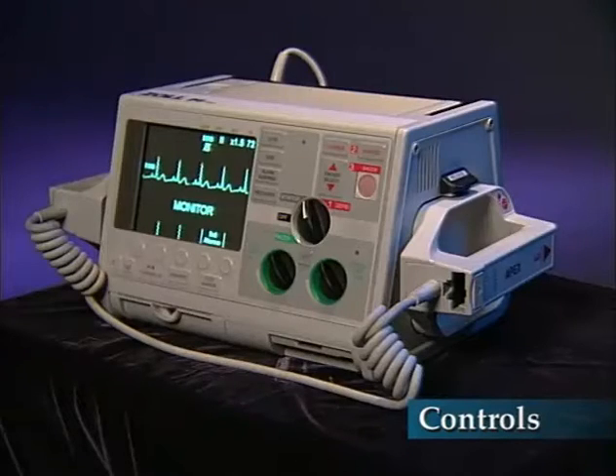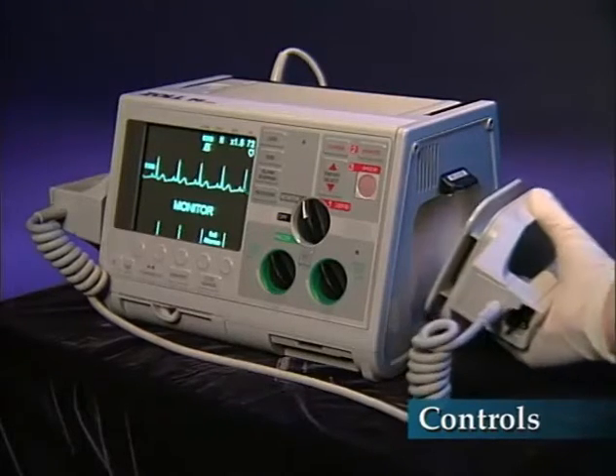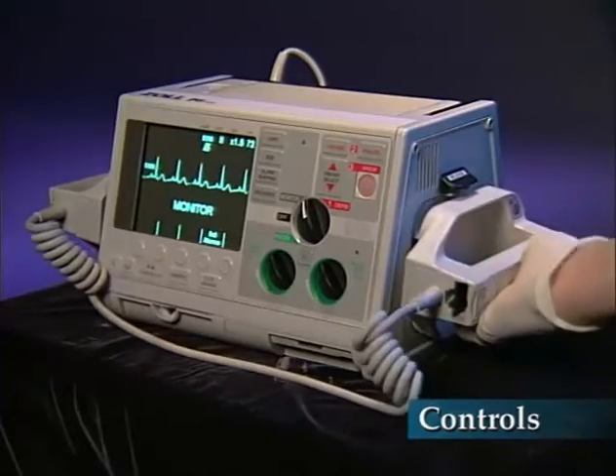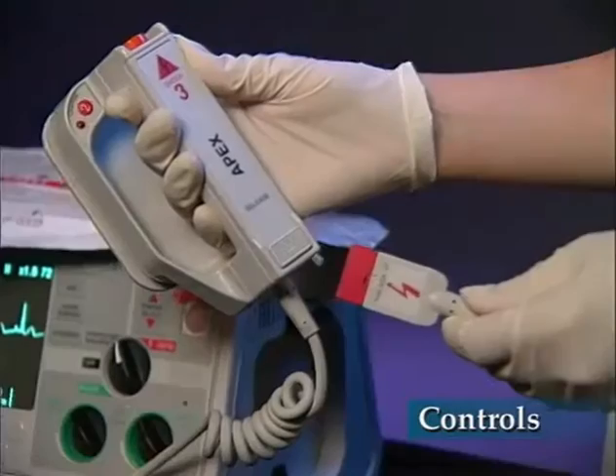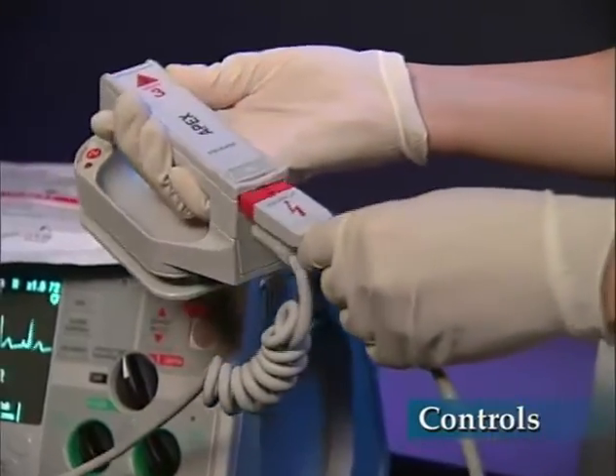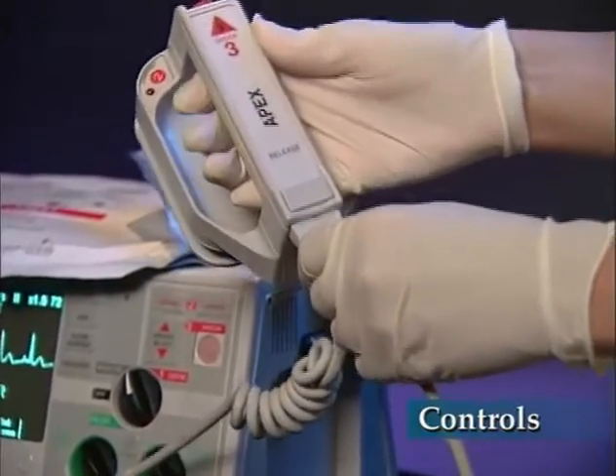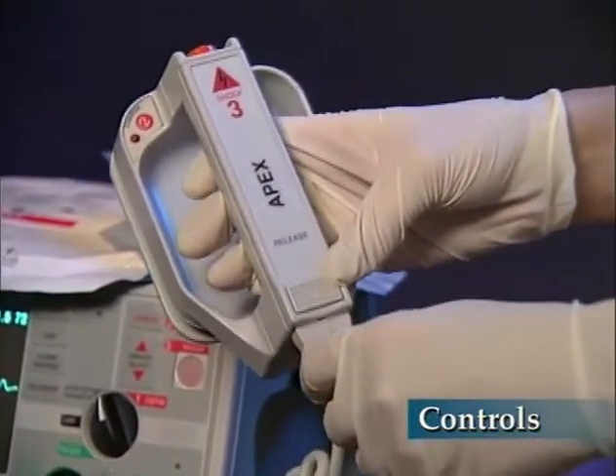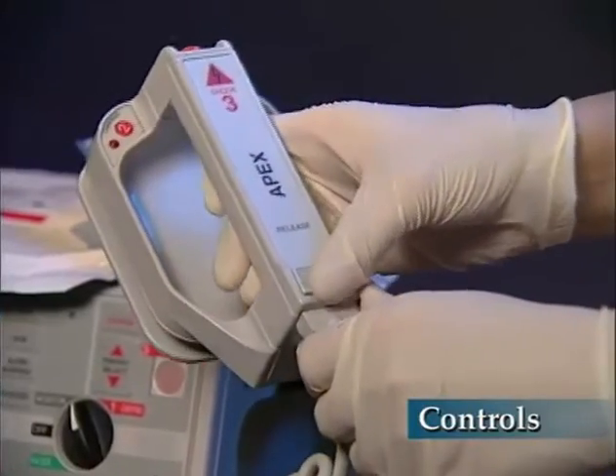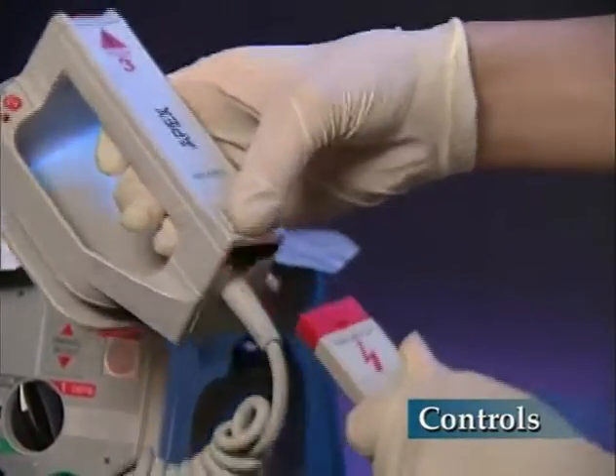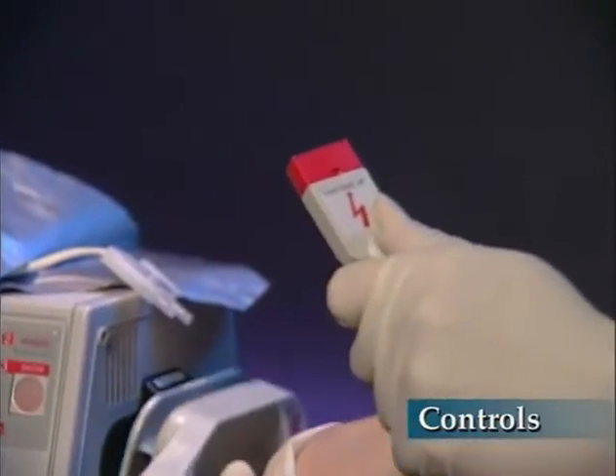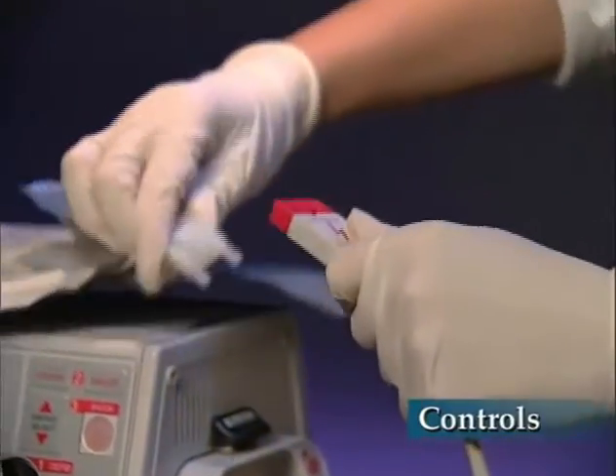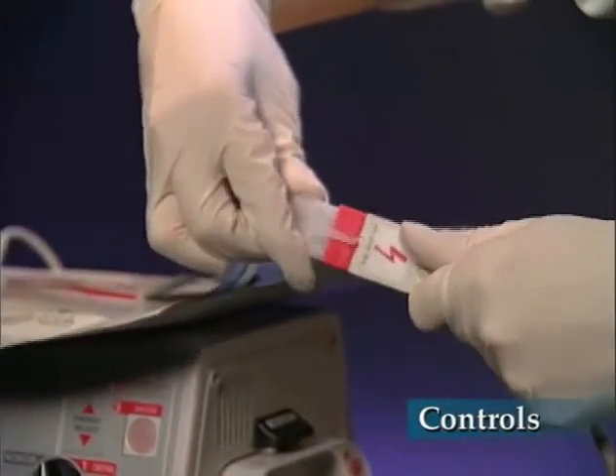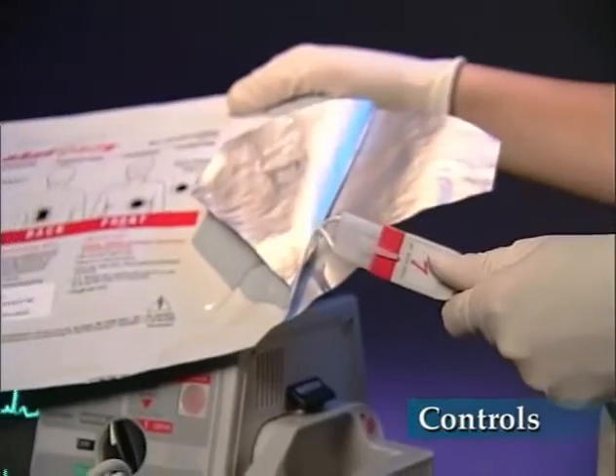External paddles are stored on either side of the unit and can be tested in this position. They may also be used as handles to grab or carry the unit. The paddles connect to the universal cable by inserting the end of the cable into the paddle labeled apex. The cable is removed by sliding the latch and removing the end from the paddles. The cable end connects directly to all ZOLL multifunction electrodes, internal handle assemblies, and the test port.